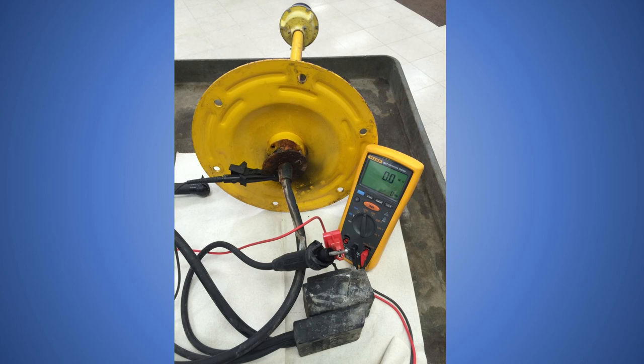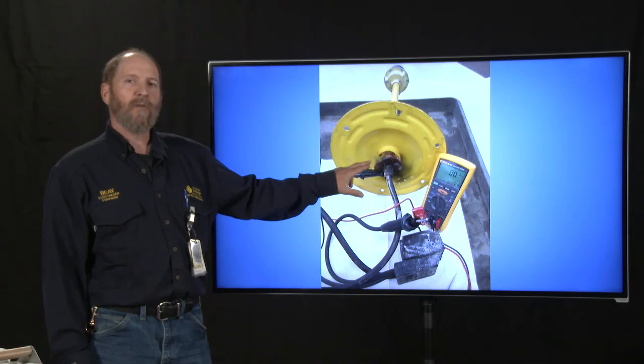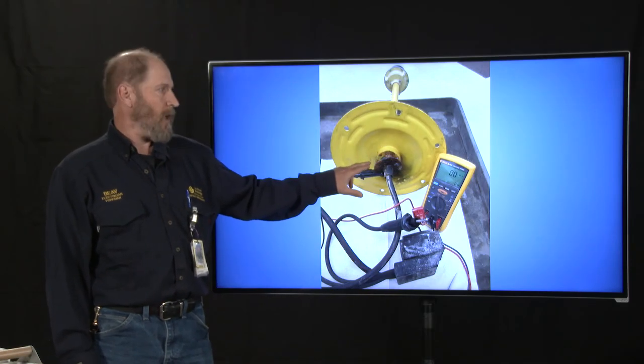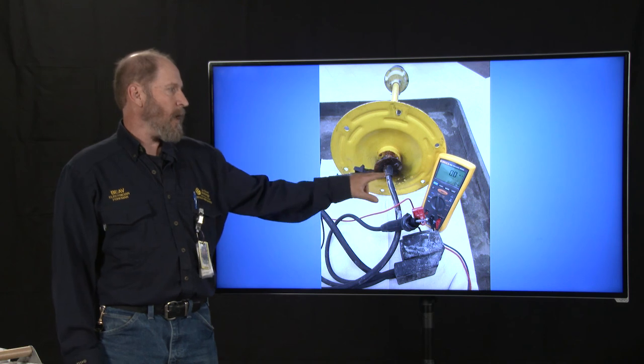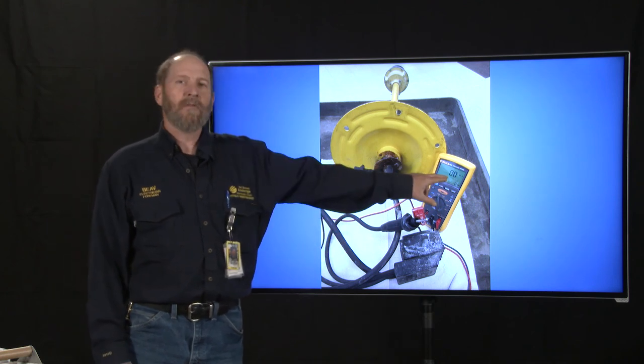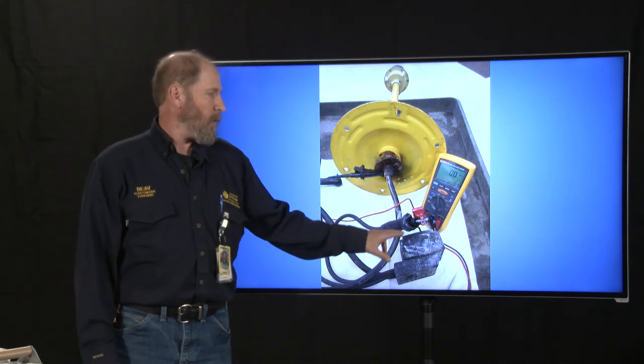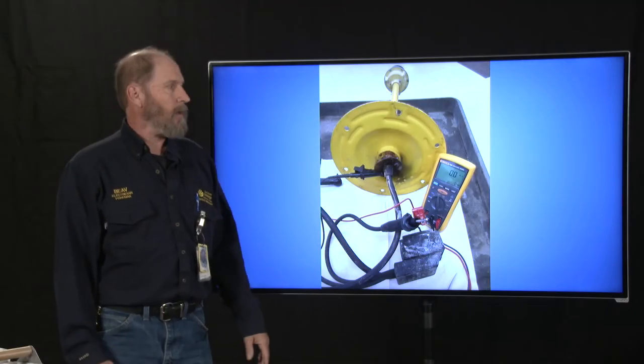This particular fixture here, you can see we are attached to the high voltage side, and we just attached it to the base of the light fixture itself. So this isn't even attached to the wire, and it's showing us 0 ohms between the primary and the light fixture. So this goes to show you that it's almost a direct connection between your 5,000 volt line and this light fixture. So that was a definite dangerous situation right there.